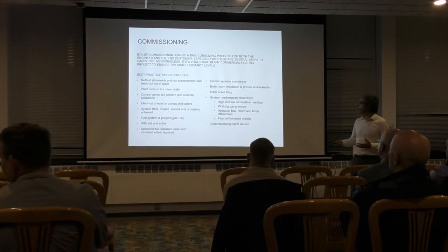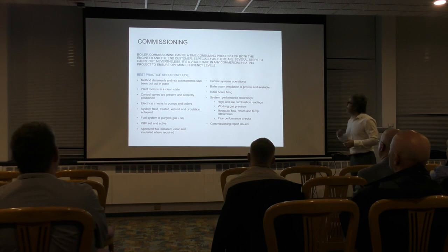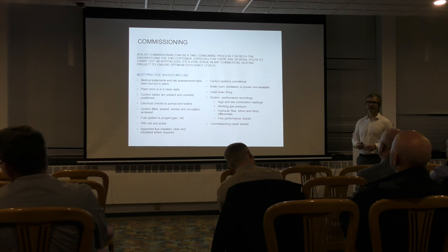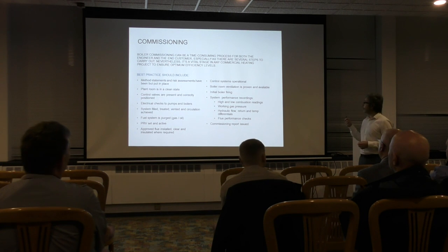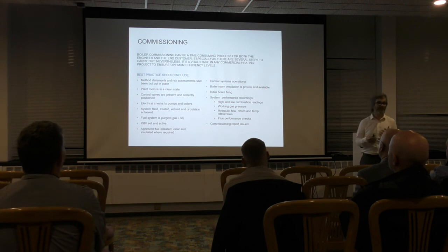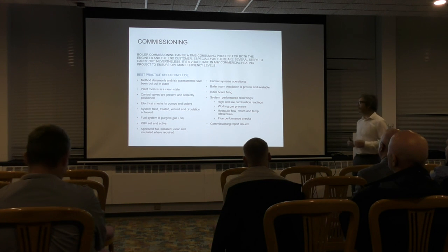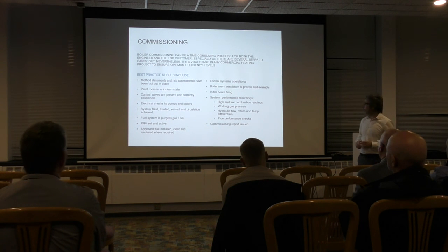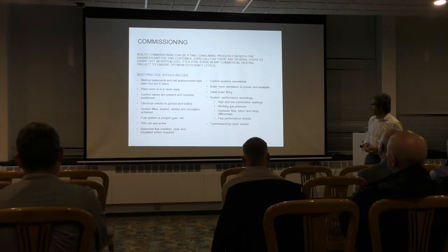And then obviously once that's all done, and everyone's happy with all that, we would then go to site. Amongst other things, the main things we do when we commission the boilers: we take high and low combustion readings, we check the working gas pressure to make sure we've got no gas pressure problems, we check the flow and return temperatures and the differentials, so we're checking the delta Ts, and then we're checking the flue performance, just to make sure the flue is performing correctly. There's no unburned gas or any products of combustion coming back down the flue. And then once we're happy with that, we would issue a commissioning report, we rubber stamp it, that then goes to the client, or goes wherever he wants to see it, and then essentially that is your replacement from start to finish.